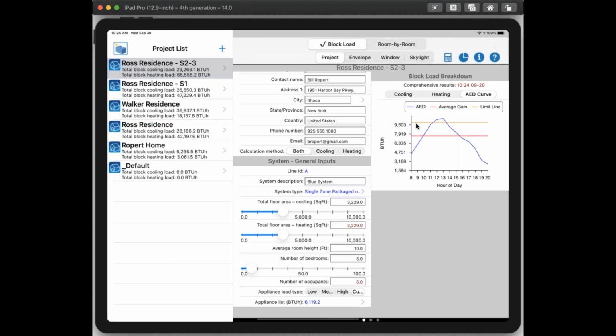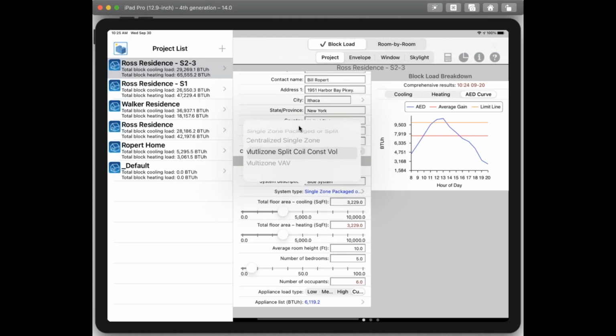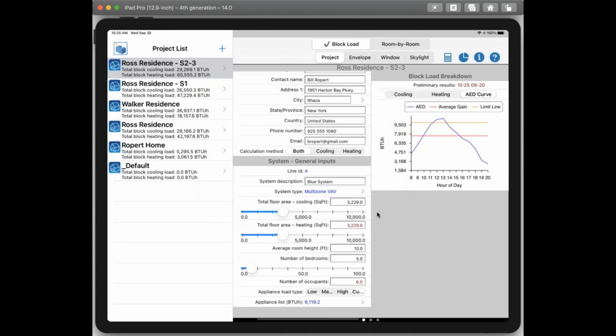Now, if this peak is greater than this limit line, that's telling me that I probably need a VAV system in this home because the load is not adequately diversified. So most likely you want to install a VAV. If this peak is below this limit line, then you're okay with a constant volume system. So that's what this curve means. And we'll also see this curve for the individual rooms. But for the whole home, ACCA is suggesting that we have a VAV system, so you would select it here, multi-zone VAV. Now, does that affect your load? No, but it will affect your equipment selection, obviously.